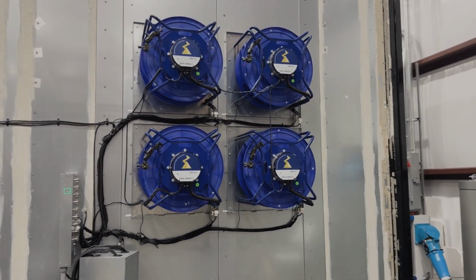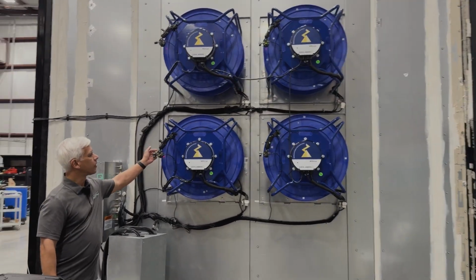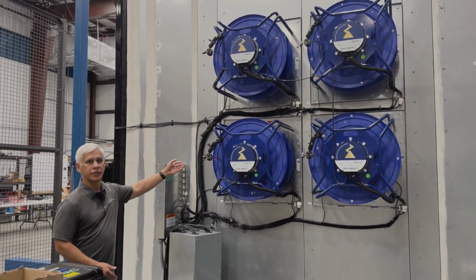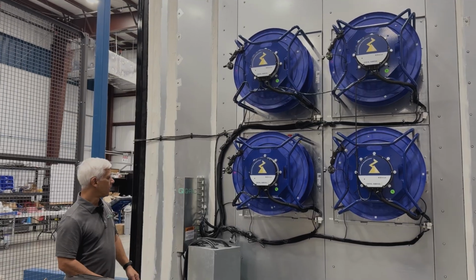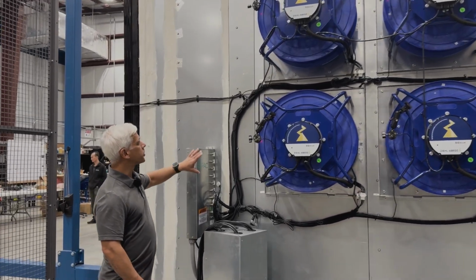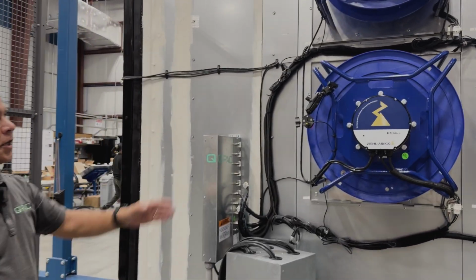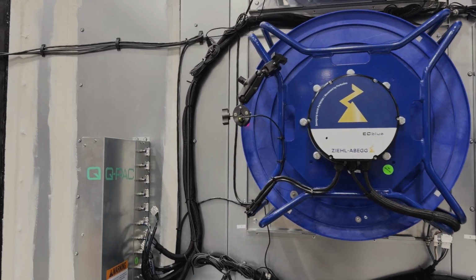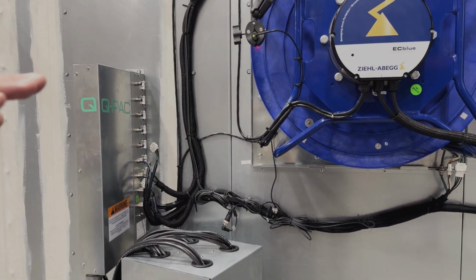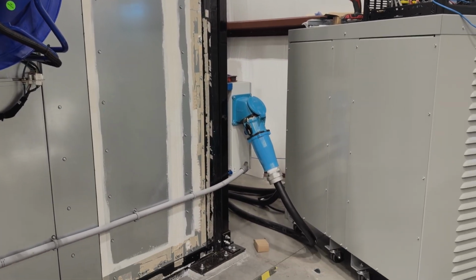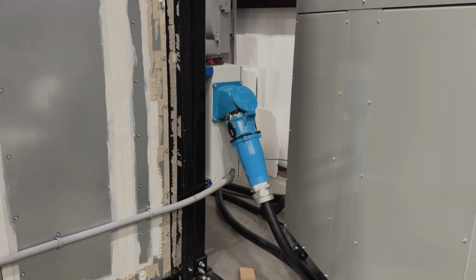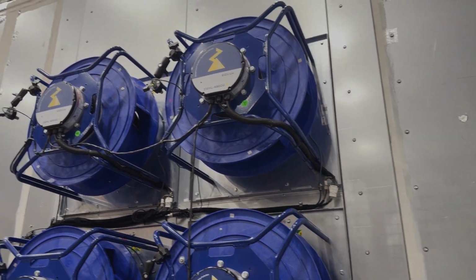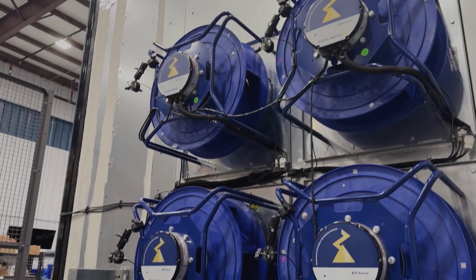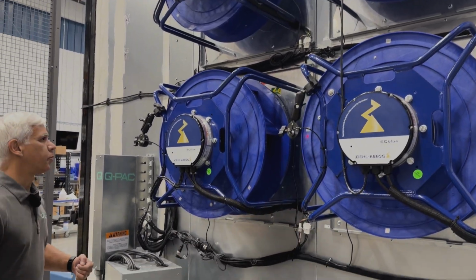We have it instrumented several different ways. We have laser tachometers here to give us an independent measurement of the speed of the fans. We have Modbus hooked up to give us instrumentation and insight into what the motor is doing. And all the way to the right, we have a giant piece of copper windings inside that shell, which lets us vary the voltage from 200 volts all the way up to 600 volts so that we can see and measure the impact of voltage on the performance of the fans.